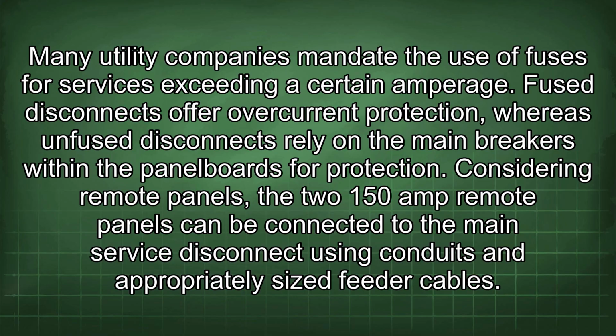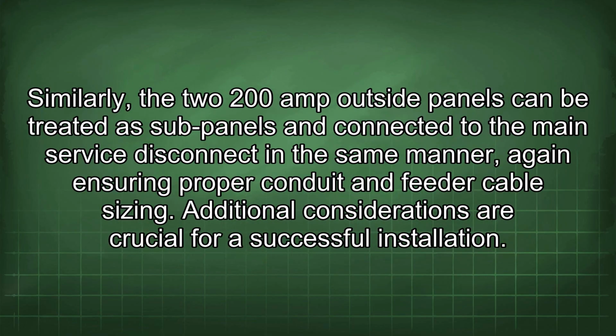Considering remote panels, the two 150 amp remote panels can be connected to the main service disconnect using conduits and appropriately sized feeder cables. Similarly, the two 200 amp outside panels can be treated as sub-panels and connected to the main service disconnect in the same manner, again ensuring proper conduit and feeder cable sizing.